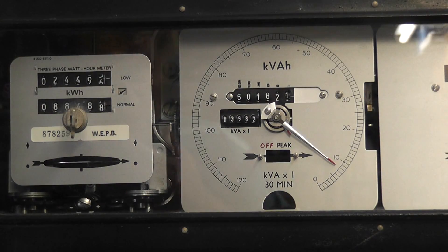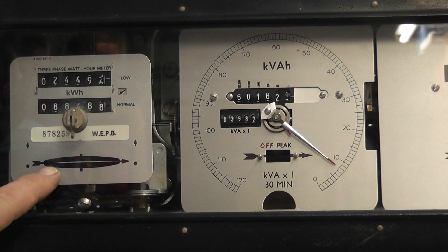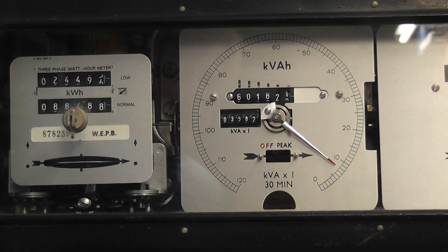As the load on this meter is resistive, and it's now increased to 9 amps, the kilowatt hour component is running very fast, while the KVAR component is running very slow.